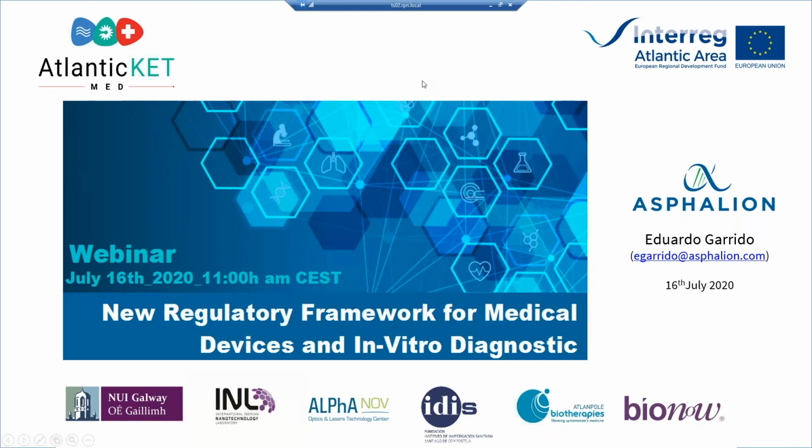So they need somebody established within the European Union who will be the authorized representative. That is not the notified body. The notified body will only assess this device and indicate if it complies or not with the regulation, but it will never act as an authorized representative.